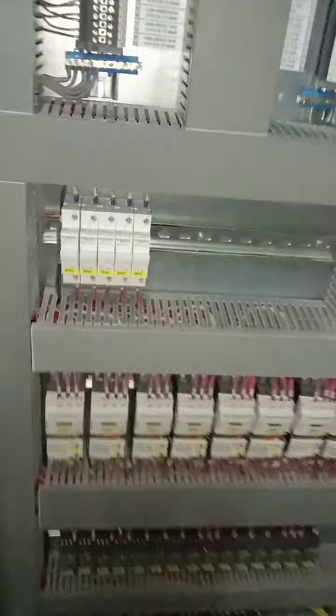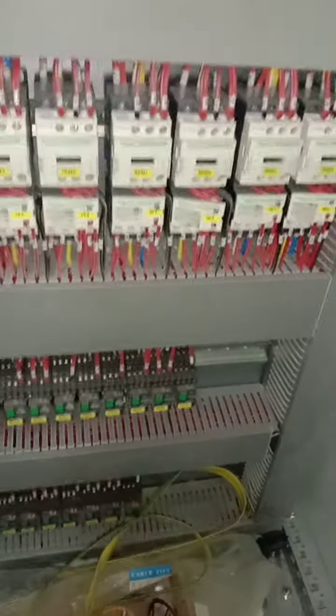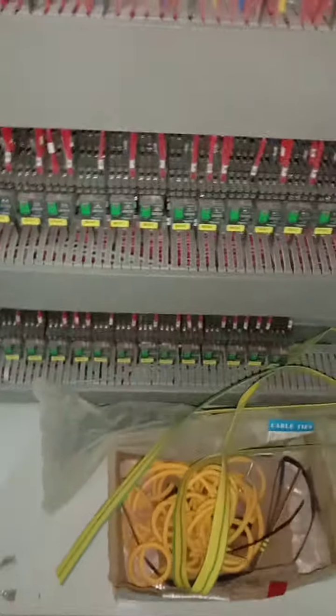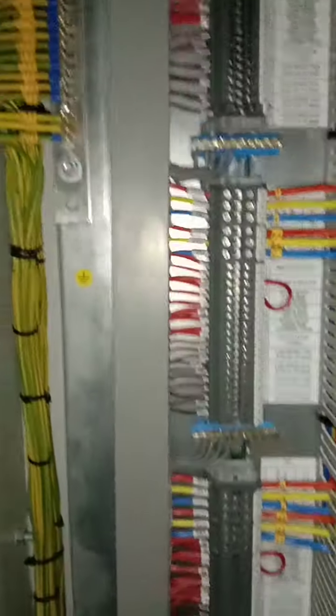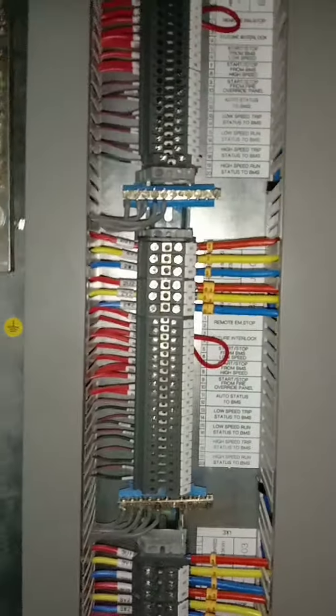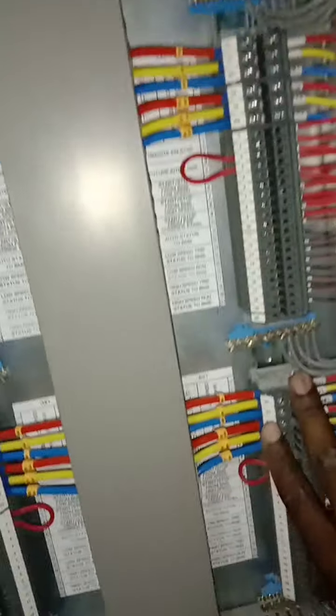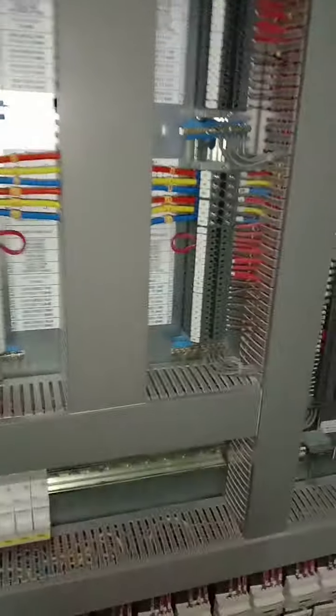On the other side now, below we have cartridge fuses, which we saw on the other side, and below we have 3-pole contactors. Below again we have single pole relays which are powered with the same 230 volts supply. And above here we have connectors, each indicating a particular motor. So this is motor 1, motor 2, motor 3, motor 4, motor 5, motor 6, 7, 8, and 9, as we saw outside on the indication lights, which are 9 different jet fans fed from this MCC. We also have the bus bar, where we have connected our earth conductors for the individual runs of cable coming from the jet fans.